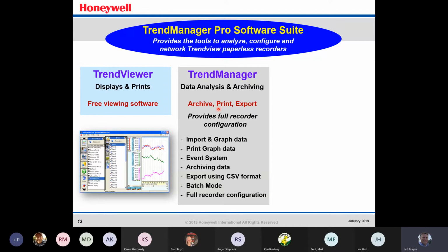The fuzzy logging will adapt to those process changes and automatically store more data during process disruptions and less data during flatline type operations. And this basically will give you the capability to record more data on the internal hard drive of the recorder. And you can enable and disable that from the Trend Manager software.